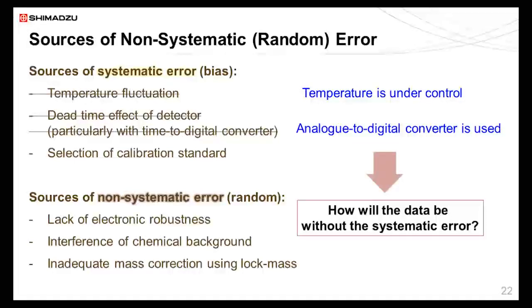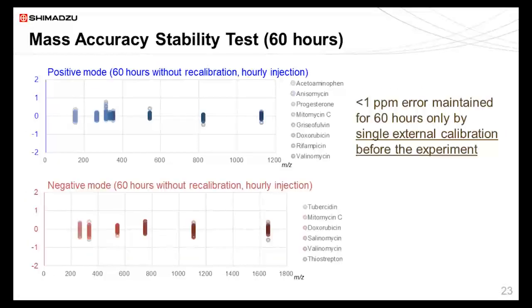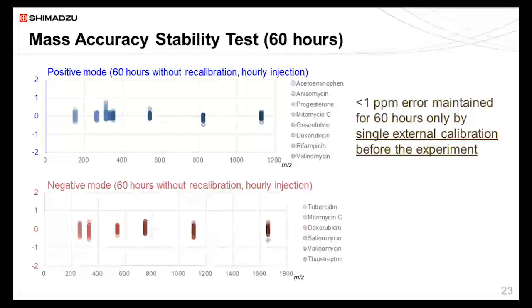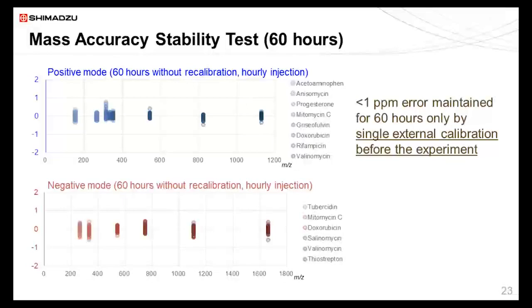So we've done another experiment, this time over 60 hours at a controlled, stable temperature environment. And this data shows the mass accuracy stability over the 60 hours. And this is only by a single external calibration conducted before the experiment. So here, the results for 14 compounds are shown, 8 positive mode and 6 negative mode. So over the 60 hours, all the data points fell under 1 ppm mass error. And individual data points show the mass accuracy at hourly measurement, and you could see that most of the data points are superimposing on top of each other, showing that the data are highly repeatable.